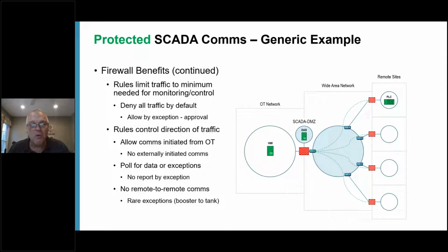So you don't want remote-to-remote communications unless it's needed. Some exceptions could be a booster station talking to an elevated tank in order to fill the tank back up as needed. For a wastewater example, you may have a level sensor upstream from inflatable dams to give advance warning so you can inflate the dams ahead of a large increase in flow going to the plant. Those are some cases where you would want to allow site-to-site communications.